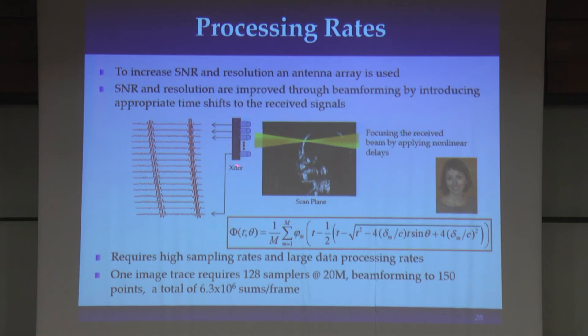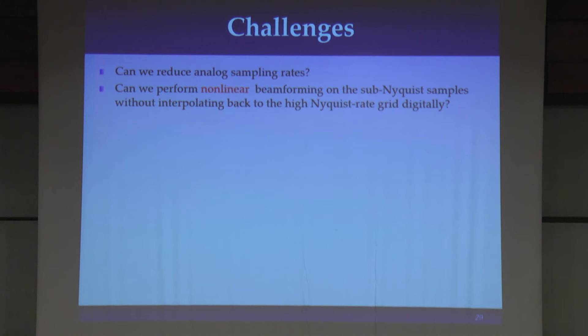In order to perform these nonlinear distortions, we have to do this on a very fine grid, which means we end up sampling at very high rates. You have to sample each one of the elements at a high rate and then combine all of the data — with 256 elements, that's a massive amount of data that has to be beamformed to every point of the image, creating a huge bottleneck. So it's not really the sampling rate that is the big bottleneck, it's the processing rate. It's not only the sampling rate we want to reduce — the question is, if I reduce the sampling rate and don't have this fine grid, how am I going to do this nonlinear interpolation once I've reduced the sampling rate?